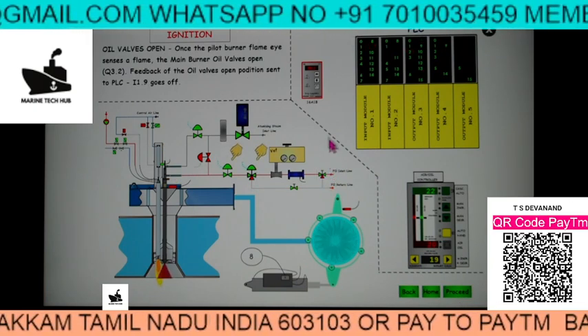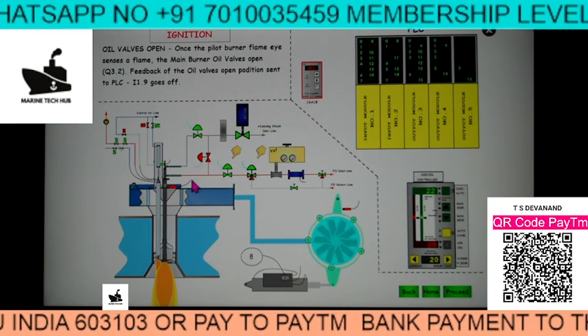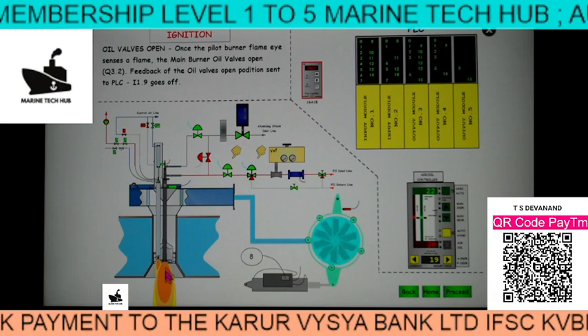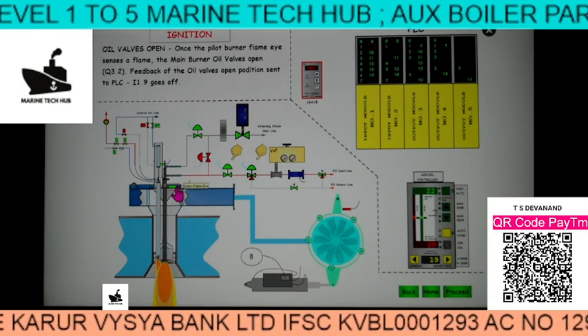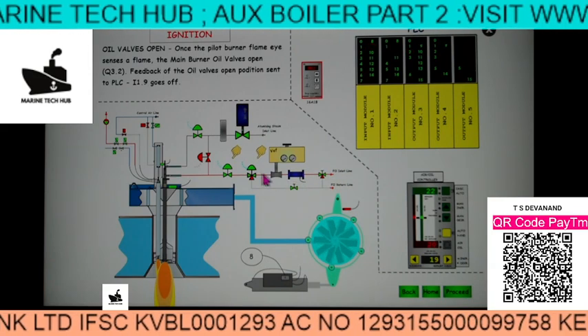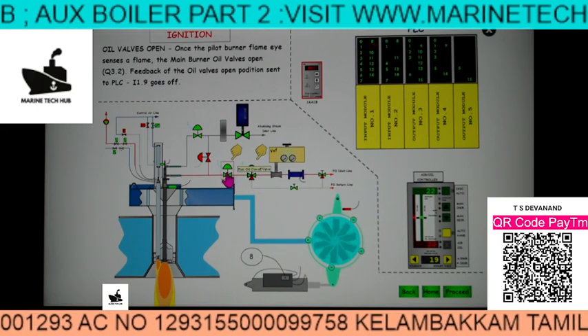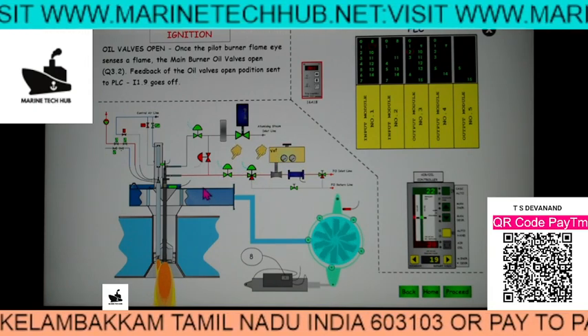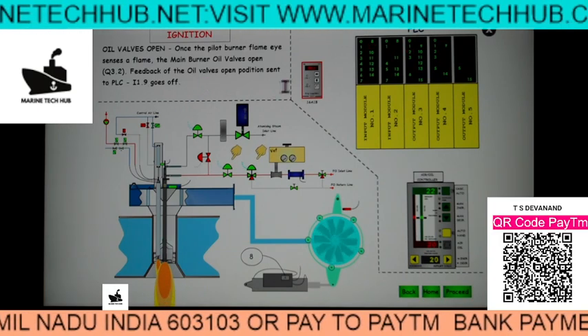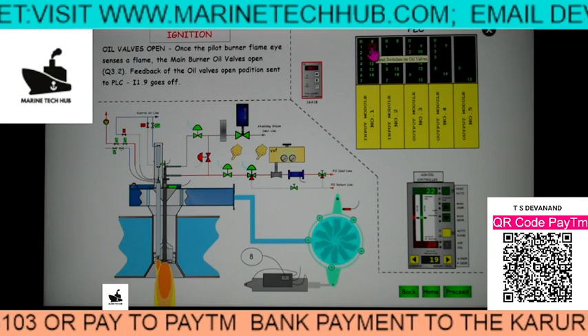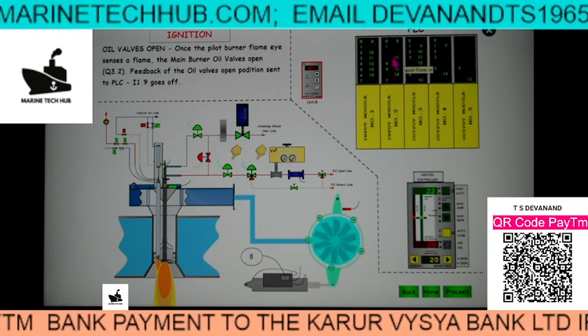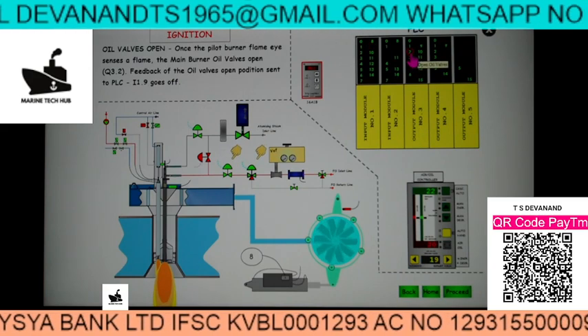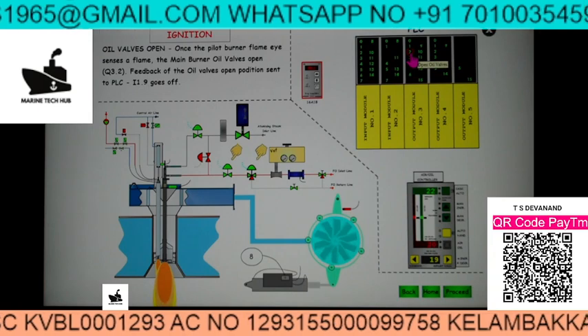Now the oil valve is opening. Once the oil valve opens, oil is flowing and with the help of the pilot burner you are able to get the flame. The main flame eye will give a signal. The oil that was going to return is now redirected — you can see it going green. The oil flow and controller are now working and signals are going accordingly. Limit switch for oil open is at 1.9 — 'oil open.' Another signal at module 3 is 'open oil valve.' This is how it is working.